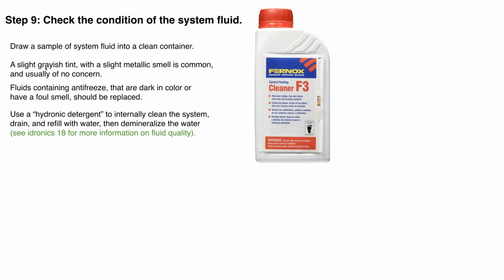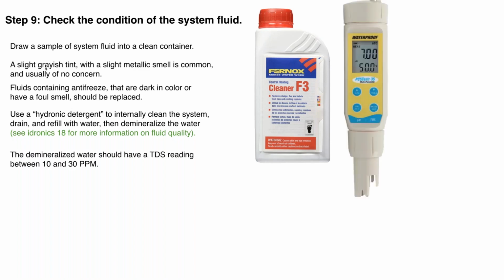And we actually did a whole issue of idronics 18, on fluid quality. It goes into more detail on this, but a good internal cleaning of the system, even a new system, as part of the commissioning process to get the solder flux, to get dirt, insects, whatever pipe gets transported today, gets handled multiple times before it gets fastened into your system, and there's likely going to be dirt or grease or something in that pipe. You want to get that out.